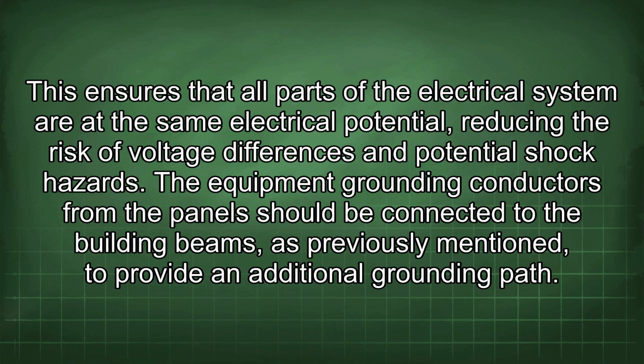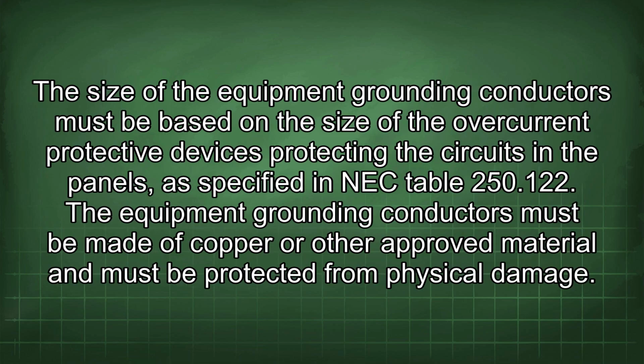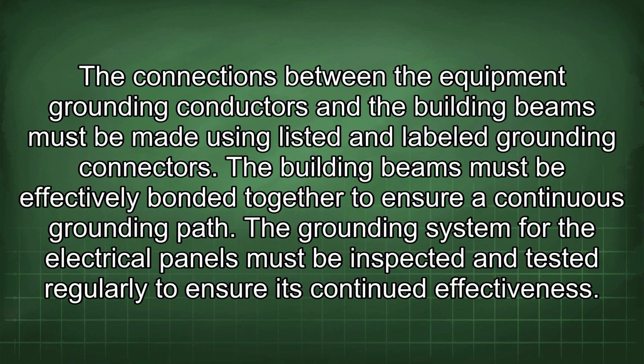The equipment grounding conductors from the panel should be connected to the building beams, as previously mentioned, to provide an additional grounding path. The size of the equipment grounding conductors must be based on the size of the overcurrent protective devices protecting the circuits in the panels, as specified in NEC Table 250.122. The equipment grounding conductors must be made of copper or other approved material and must be protected from physical damage. The connections between the equipment grounding conductors and the building beams must be made using listed and labeled grounding connectors. The building beams must be effectively bonded together to ensure a continuous grounding path.